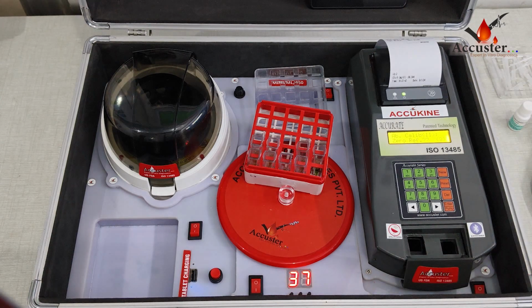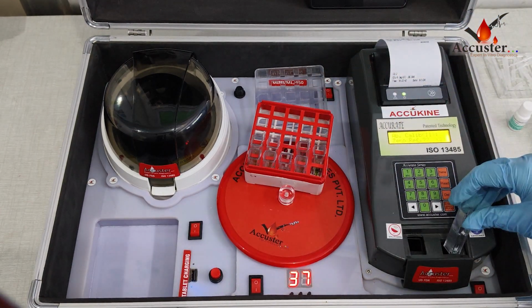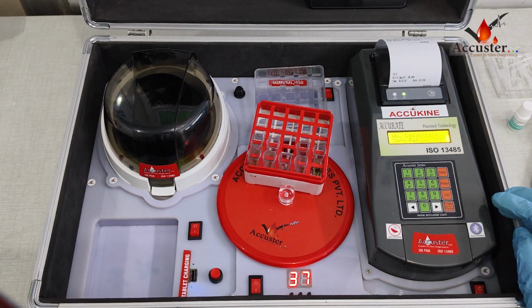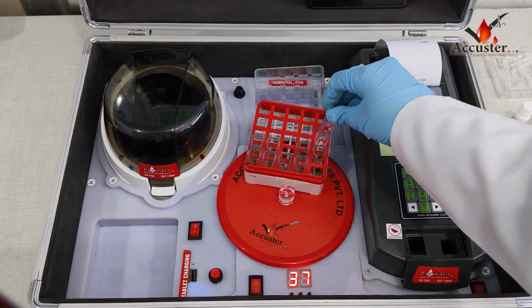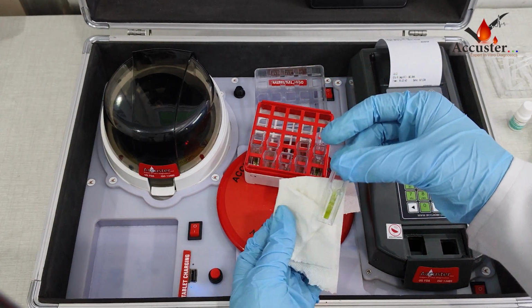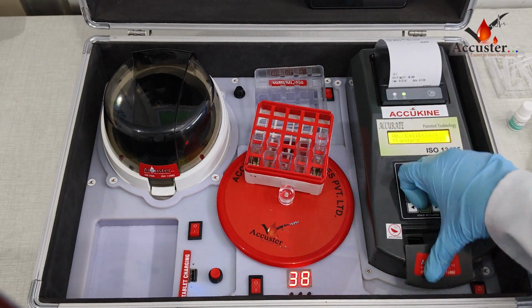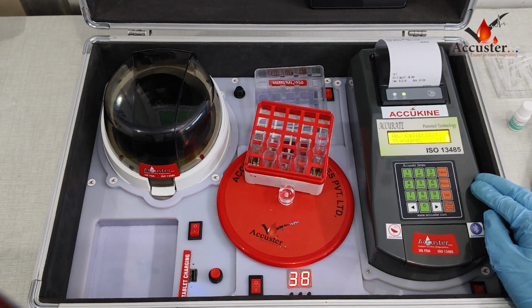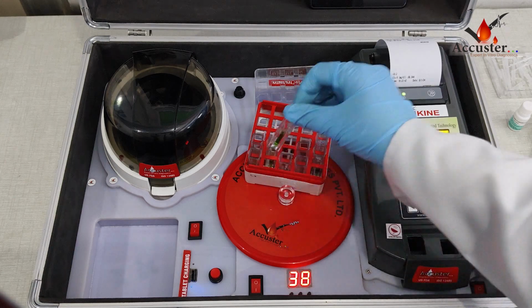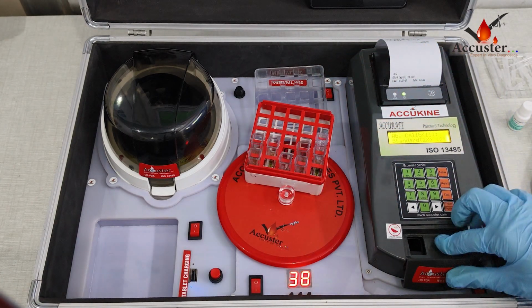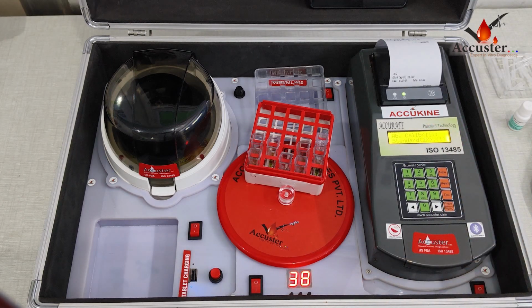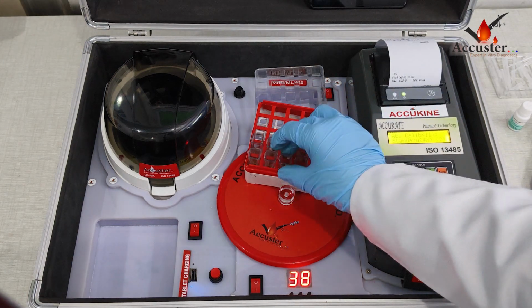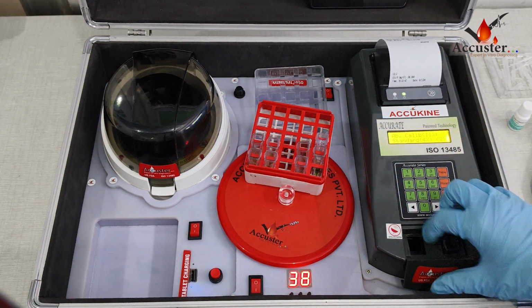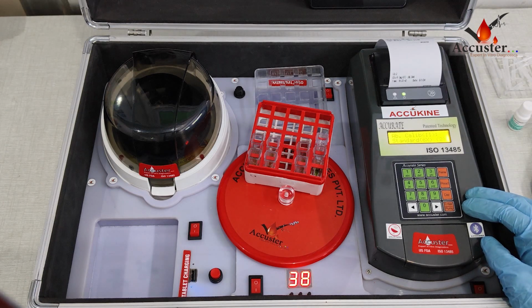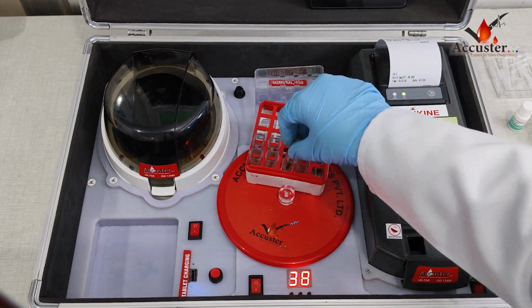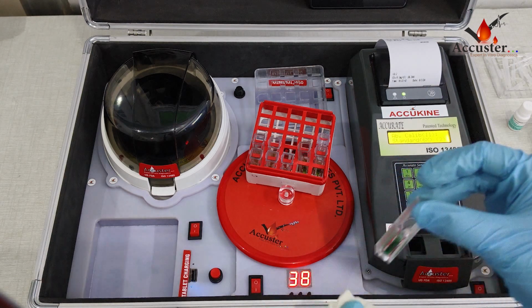Machine will ask for 0 reference. To set 0 reference, we will put the cuvette with distilled water and press enter. For standard, take 1x cuvette and then press enter. After that, 2x cuvette, then press enter. Now 4x cuvette and press enter. For each cuvette, only 2 seconds are needed for calibration. Calibration is done. Lastly, 6x cuvette and then press enter.